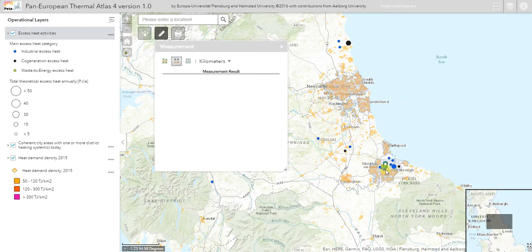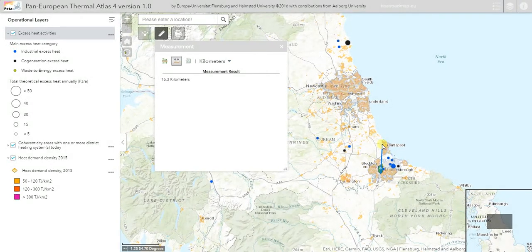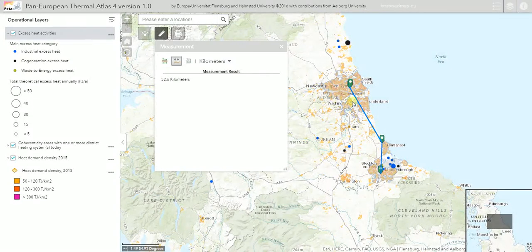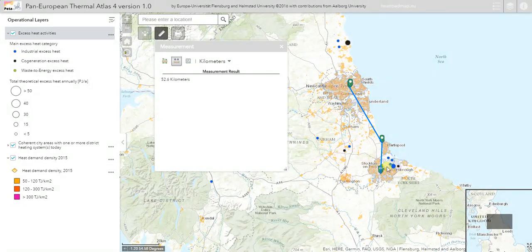Taking Middlesbrough as a starting point, the long-term strategy could be to go through Hartlepool up to Newcastle — a distance of approximately 50 kilometers, matching the Swedish example. The heat demand in Newcastle is about 30 petajoules and in Middlesbrough about 10 petajoules, while the excess heat in Middlesbrough alone is over 30 petajoules, with additional excess heat available north of Newcastle. Planning this area as a region means the combined excess heat between Middlesbrough and Newcastle would be more than sufficient to replace all the gas currently used across Newcastle, Hartlepool, and Middlesbrough.